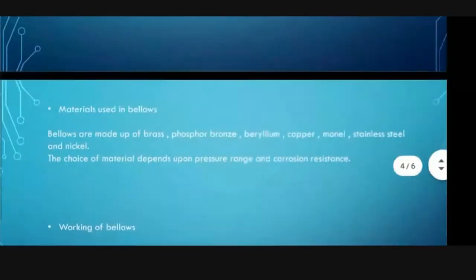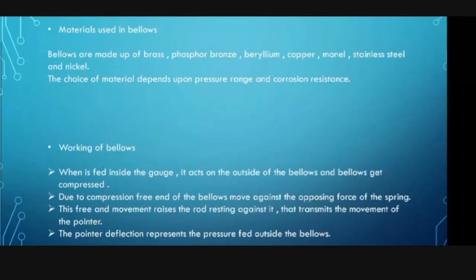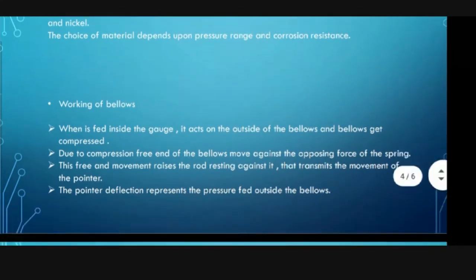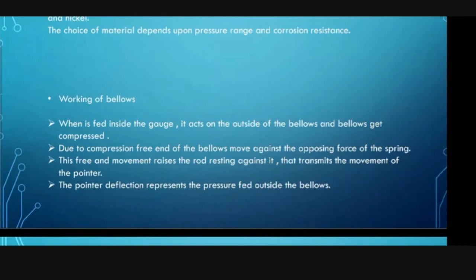Change the slide. Materials used in bellows. Bellows are made of brass, phosphor bronze, beryllium copper, monel, stainless steel, and nickel. The choice of material depends upon pressure range and corrosion resistance. So, working of bellows. When pressure is fed inside the gauge, it acts on the outside of the bellows, and the bellows gets compressed. Due to compression, the free end of the bellows moves against the opposing force of the spring. This free end movement raises the rod resting against it, which transmits the movement to the pointer. The pointer deflection represents the pressure fed outside the bellows. Over to you, Ayush.